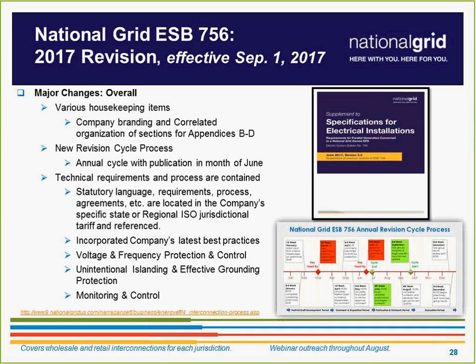For voltage and frequency control, we basically align with what IEEE 1547 says—that's our rule. For islanding, as I mentioned before, we have new methods of anti-islanding protection. Before, we only had a couple of allowable interconnection schemes. Now everything aligns with what Massachusetts or other states are doing. For recloser control, this is basically for active use—we distinguish and clarify the language on where and how that will be required.